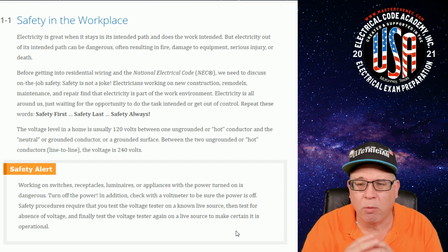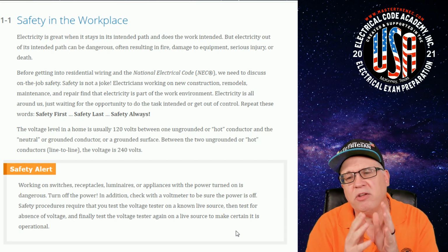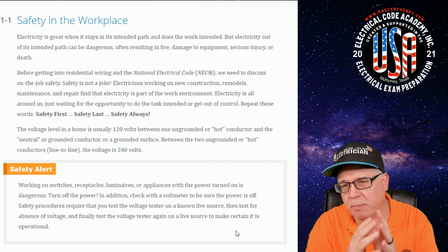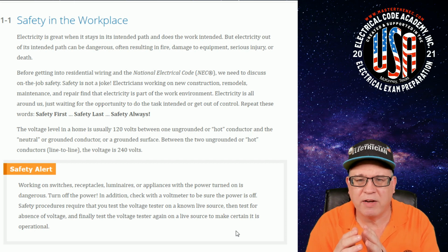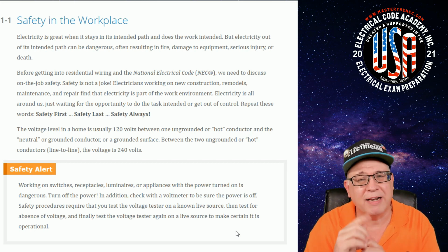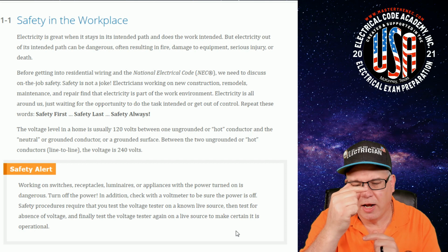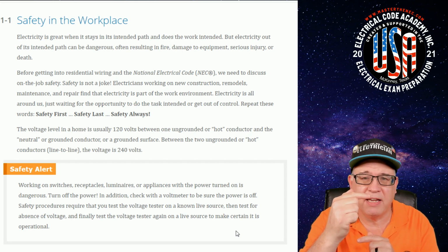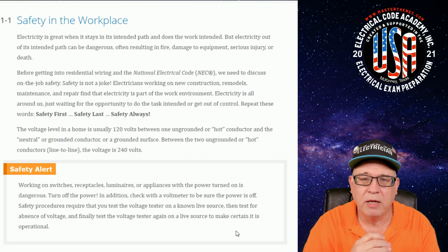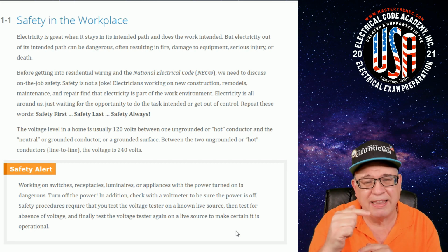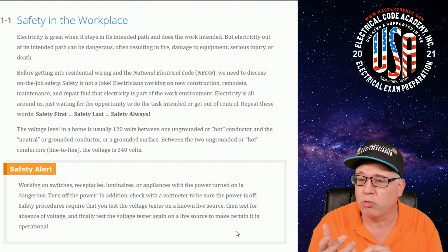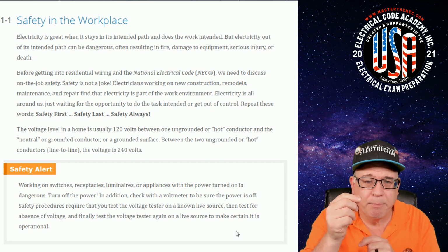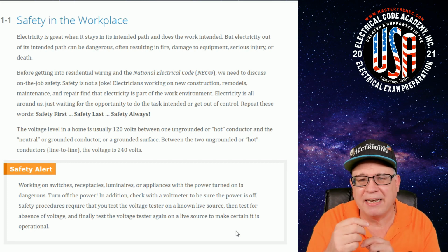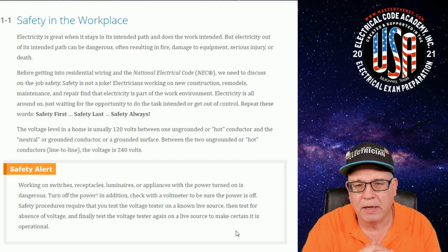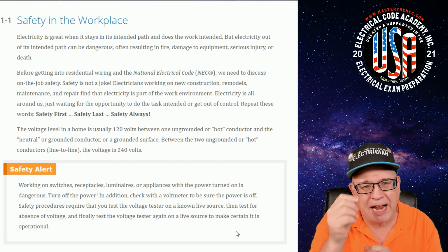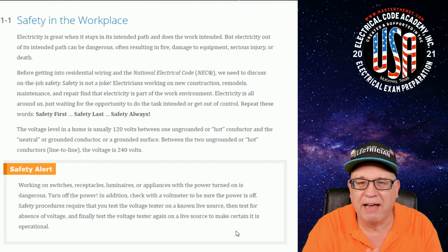Think about how that works in a transformer. We're talking about the single winding used to supply power to a residence. The winding at the secondary has a potential between the two points at opposite ends of 240 volts. With 120, we tap midway - that's why we traditionally bring 3 conductors down to a residence. From that midpoint to either end of the winding, you get 120 volts. You're tapping that 240 right in the middle. Hence, 120 is half of 240.